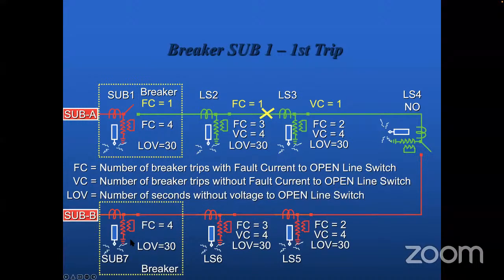If you have read about protection, many faults in distribution systems are temporary, and generally they are cleared by themselves. Maybe there is too much wind and two lines are touching each other. So it is a temporary fault and then it will be cleared. Generally they have a recloser with three tries. It will open and close once, then a second time, open and close, and by the third time, if the fault is still there, then the breaker will stay open and it declares that there is a permanent fault. That is generally the normal operation everywhere.